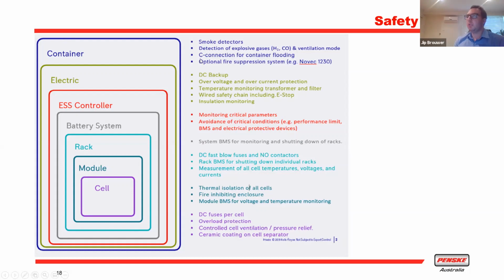On the container level, which is more relevant, we have smoke detectors. We also have detectors for gases, mainly hydrogen, and carbon monoxide in case of fire. In the worst case, we have a nozzle where the fire department can attach a water hose and flood the whole container with water, which will definitely stop the fire. Or we can have additional fire suppression systems using a chemical called Novec 1230, which in essence takes away all the oxygen around the cells, killing the fire that way.